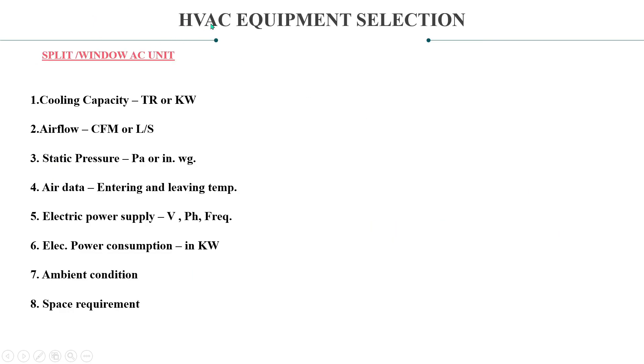How do you select the split or window AC unit? First, you have to measure the cooling capacity, which can be measured in tonnage of refrigeration or kW. Air flow can be measured in CFM or litres per second. Static pressure in Pascal or inch water gauge. Air data covers entering and leaving temperature of air. Electric power supply — it could be in volts, phase and frequency. We have 230V and 415V; mostly we use 230V, but this depends on your country. Phase — whether it's single phase or three phase. Frequency — what is the frequency of the machine.